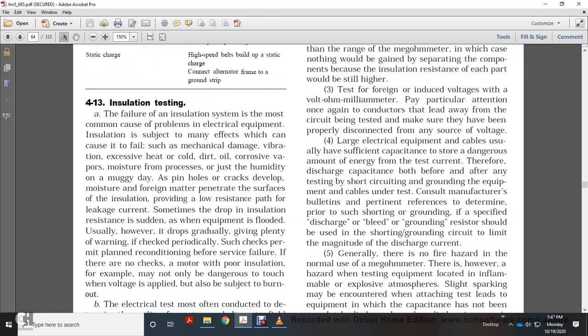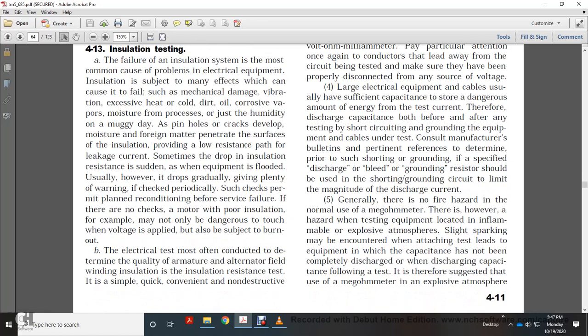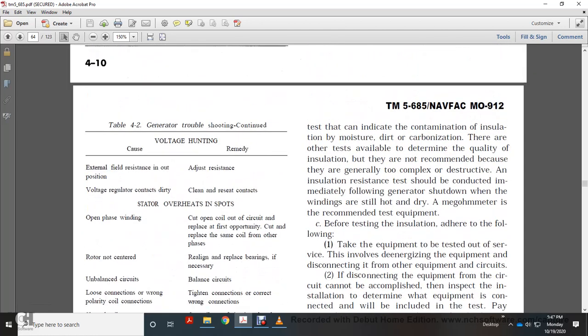With the warning given, check periodically. Such checks permit planned reconditioning before failure. If there is no check, a motor with poor insulation, for example, may not only be a danger to touch when voltage is applied, but is subject to burnout. Electrical tests must often be conducted to determine the quality of the armature, alternator, and field winding insulation. An insulation resistance test is a quick, convenient, non-destructive test that indicates contamination, moisture, dirt and carbonization of the insulation.